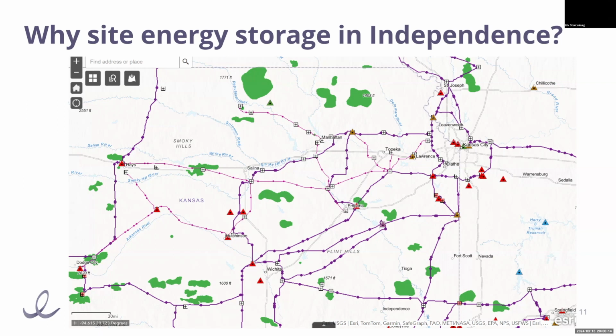So if we actually put the battery in Kansas City or on the east side of Kansas City, like we do in Independence, it means we can soak up all this extra wind energy all night from any of these transmission lines, even potentially from a coal plant that wants to run at a higher operational level for better heat rate efficiency. And regardless of the condition of the transmission system the next day, when we discharge that energy to serve businesses and residences, it's going right into the load pocket.